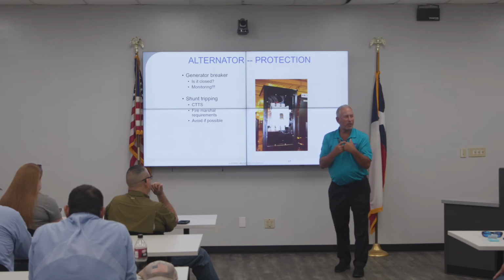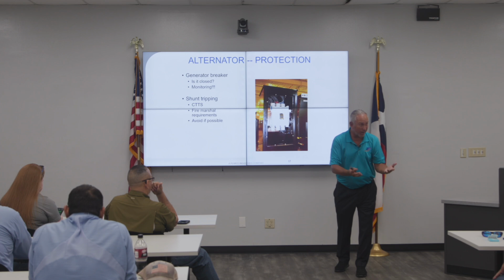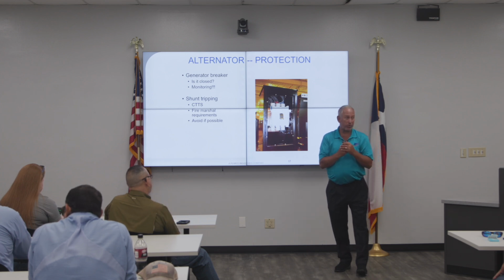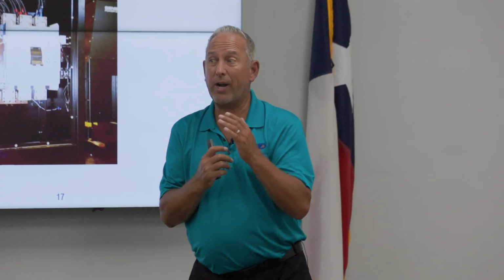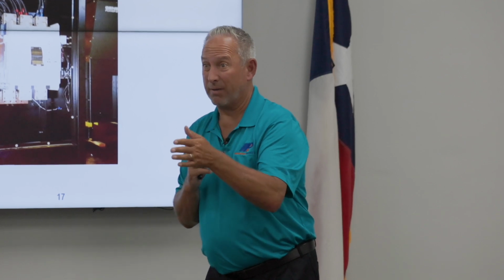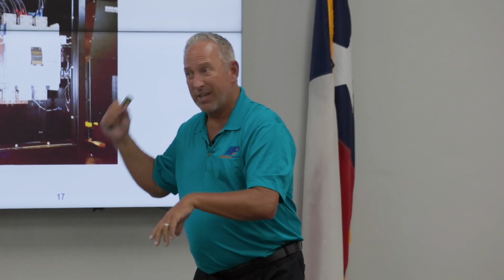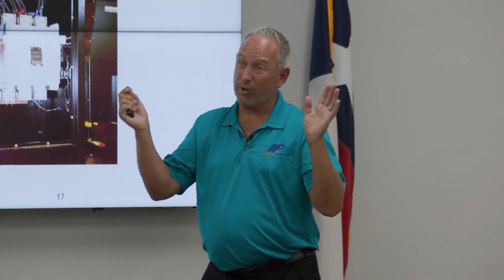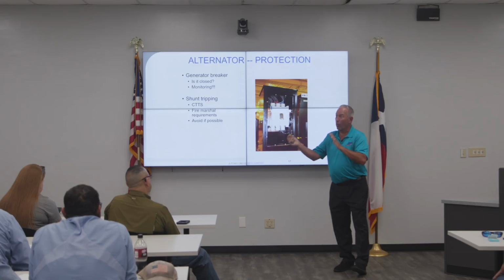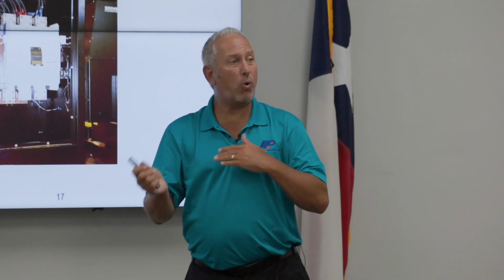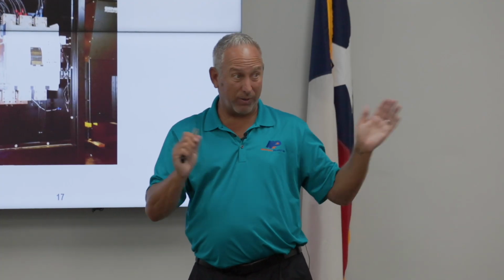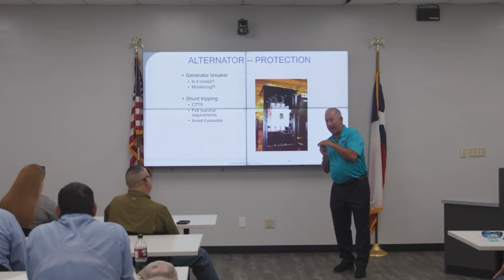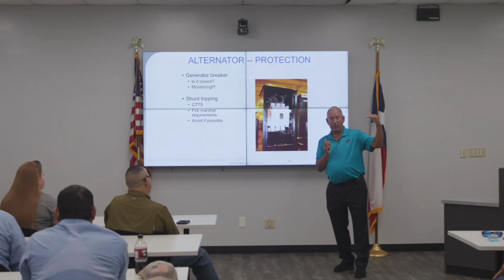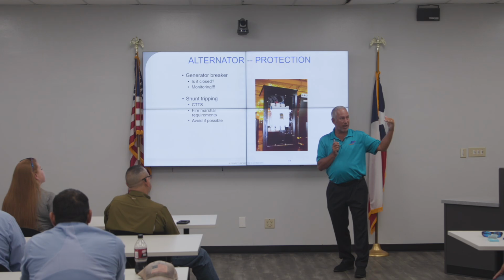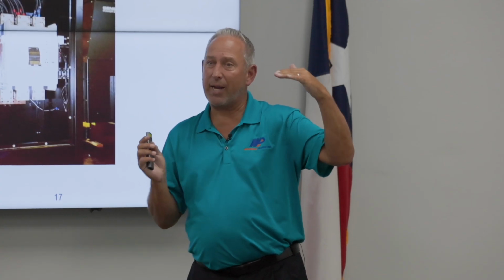If you've ever noticed the utility will come back sometimes and then goes out right away, they're doing reclosures, is what that's called. What they're trying to do is they're trying to blow things off the line, right? So they'll close it just to send a jolt down the line to clear a limb or whatever the case may be. Or they're just switching to different grids, trying to get power back to you. So you don't want your building exposed to all that jumping around stuff, right? So that's when we say, hey, stay there for 15 minutes, 30 minutes, then you know the utility is going to stay there. So the transfer switch goes, okay, you're good.